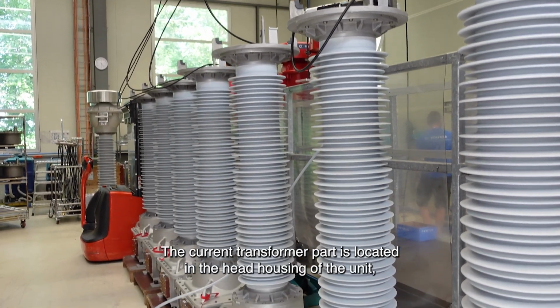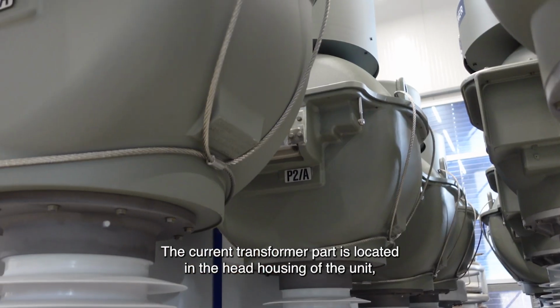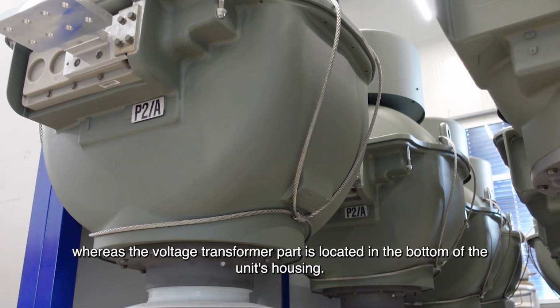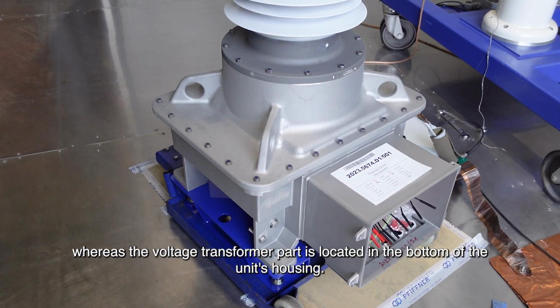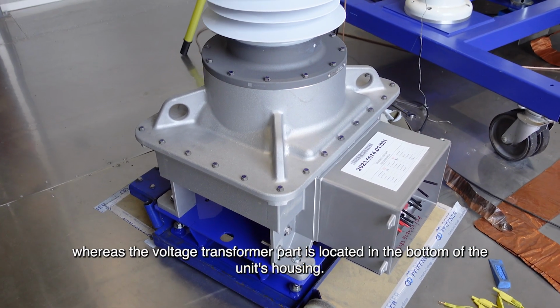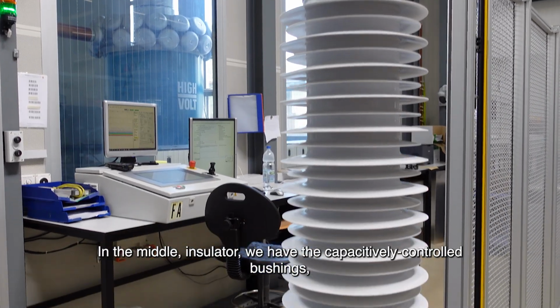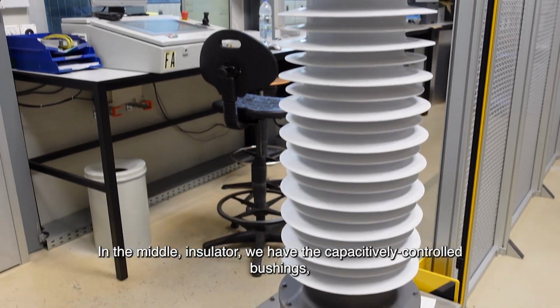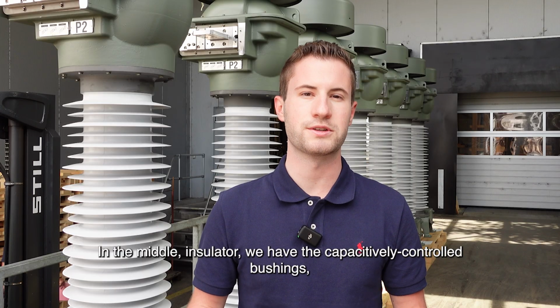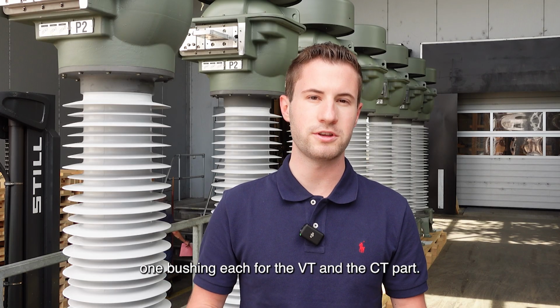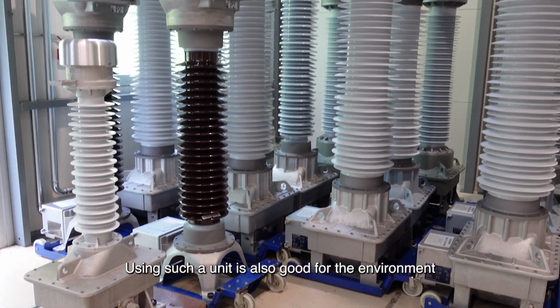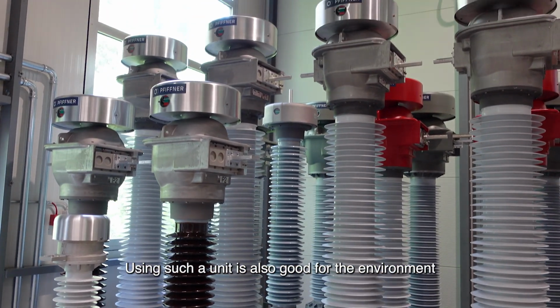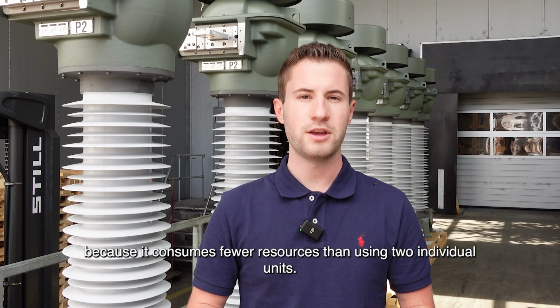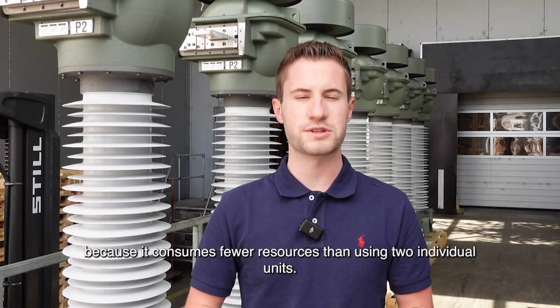The current transformer part is located in the head housing of the unit, whereas the voltage transformer part is located in the bottom housing. In the middle, in the insulator, we have the capacitively controlled bushings, one bushing each for the VT and the CT part. Using such a unit is also good for the environment because it consumes much fewer resources than using two individual units.